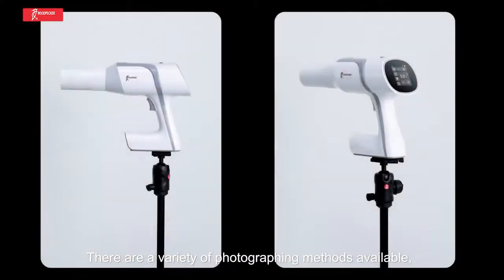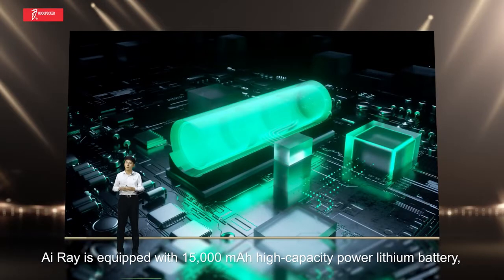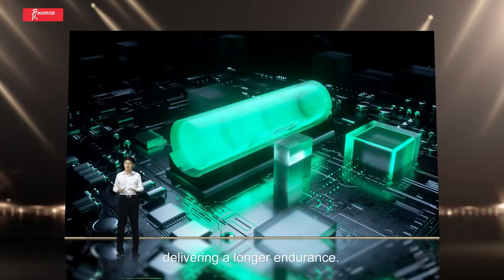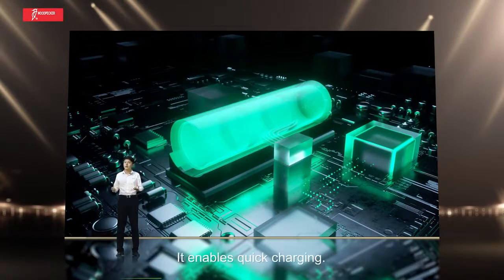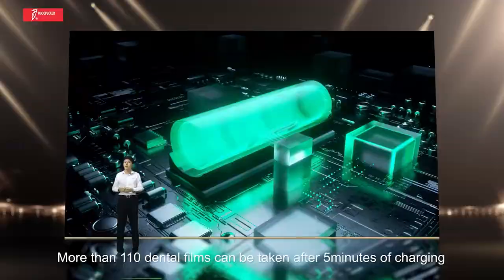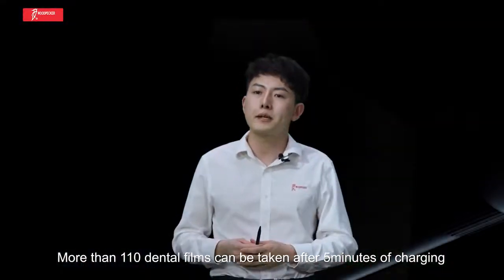There are a variety of photographing methods available, contributing to safe and more free operation. AI Ray is equipped with a 15,000mAh high-capacity lithium battery for longer endurance — more than 1,500 dental films can be taken on a full charge. It also enables quick charging; the machine can be used after just 5 minutes of charging, allowing more than 110 dental films to be taken.